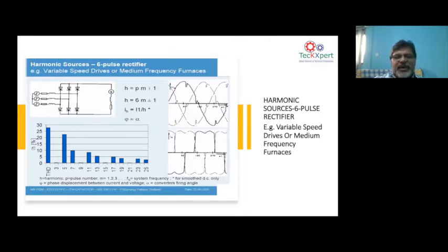As I said in the previous one, h = np plus minus 1, you can see the same equation here again. You have a 6 pulse drive, which has 6 diodes, and you go back to the equation h = np plus minus 1, 6 plus minus 1 is the 5th harmonic and the 7th harmonic. So if you look into your harmonic spectrum, you can see 5, 7, 11, 13, all characteristic harmonics of a 6 pulse drive. And it also talks about the sum of all the harmonics as a THD graph, because that is how you ultimately try to understand the harmonic indices. With harmonic indices, one is the total harmonic distortion, and second is the individual harmonic distortion. So on a magnitude versus frequency spectrum, you can see this as a bar graph.